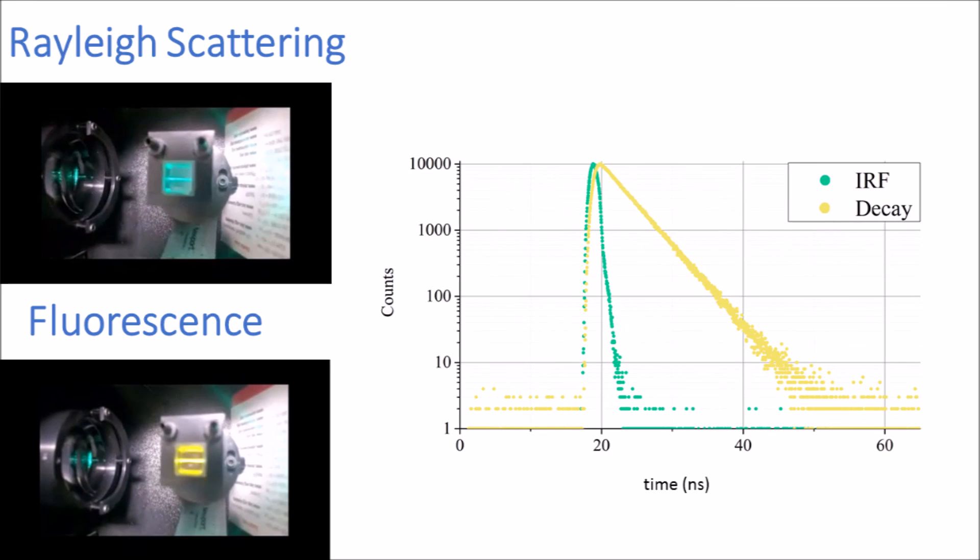The fluorescence decay is generally of an exponential form such as that shown. For convenience, it's often plotted in a log scale because the log of an exponential is a straight line, and we can fit this data to get the fluorescence lifetime. The lifetime is the time it takes for the intensity to fall 1 over E.